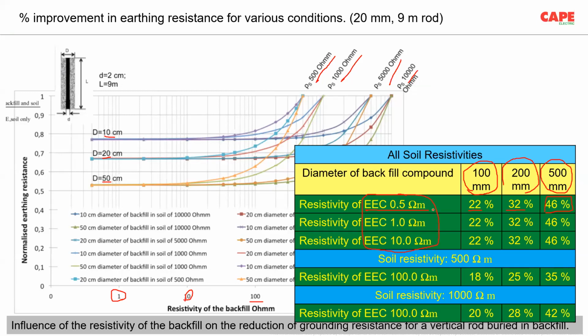With 0.5 ohm meter, the same value. 1 ohm meter of the earth enhancing compound, the same improvement. 10 ohms of the earth enhancing compound, the same value. So what is important is that the resistance of the earth enhancing compound is not very important, but the area with which you are filling is more important.